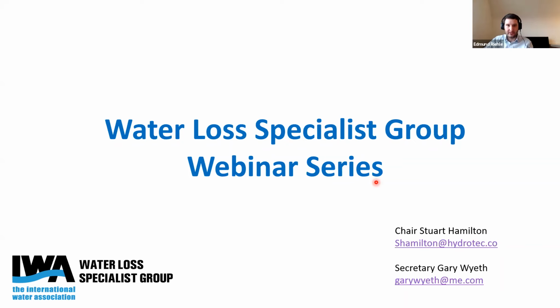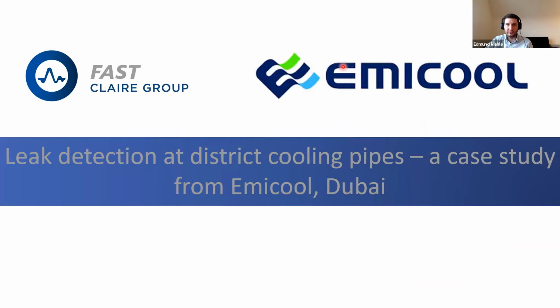Yes, as Gary already said, I will present a case study from Dubai, Emicool, where we did a leak detection project at district cooling pipes. And as you know, probably, on cooling pipes it is very difficult to apply our ordinary acoustic technology to detect leaks, because you have lots of noises on the pipes due to condensers, pumps, and heat converters. So it's really difficult to detect and locate there.